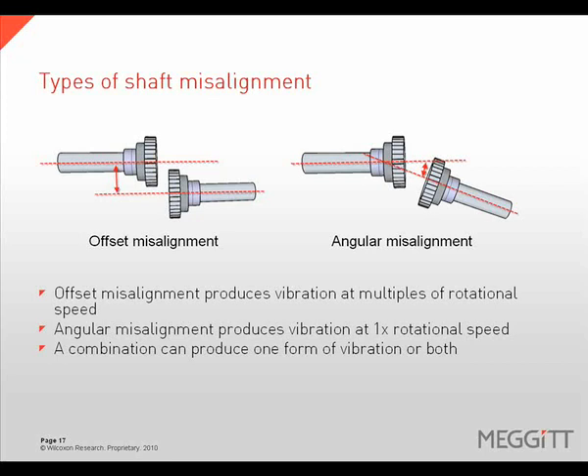Angular misalignment will commonly produce a vibration response at 1x rotational speed, with the axial direction often being the highest in amplitude. While this is often the case, it is not always true. Depending on the coupling type employed, the vibration response may vary from one machine to the next.